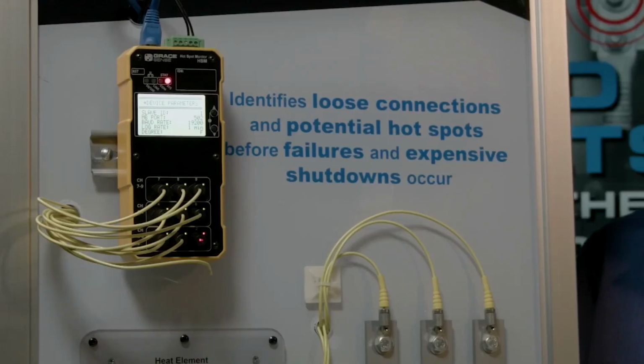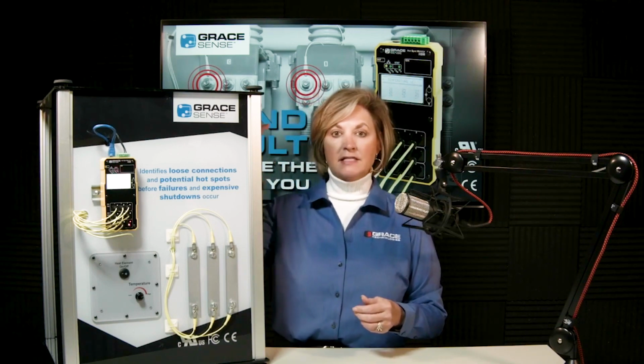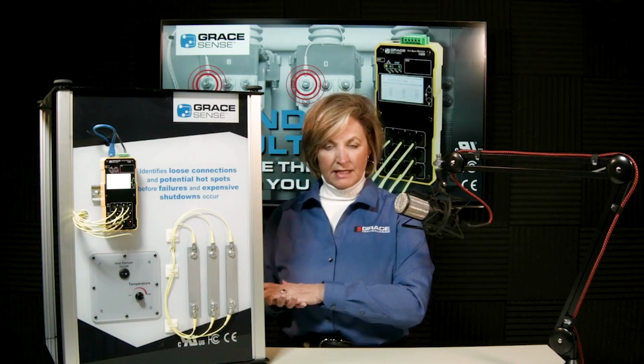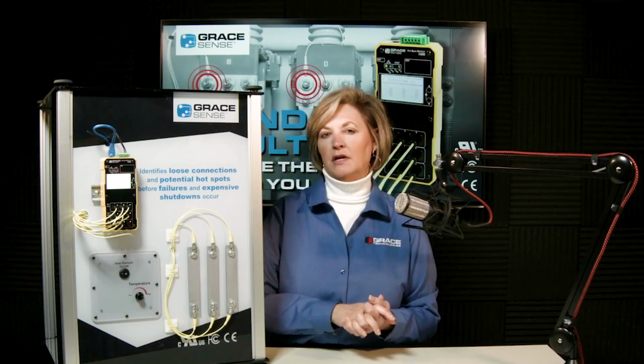So of course, then we don't want it to melt. If a delta T calculation is desired, we do have a solution to measure ambient. So there's two types of ambient connectors, if you will. One is a curved ambient holder for inside the equipment, and one is a standoff for perhaps on the profile of the equipment. So you know what's going on inside the equipment and what's going on outside of the equipment.